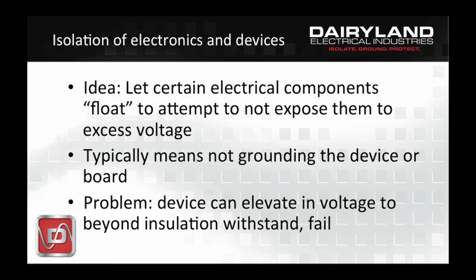Electronics and their failures can be associated at times for users with lightning events and AC fault events. Sometimes in order to deal with that, users might think of leaving their electronics to float electrically and not bond them to certain structures in an attempt to isolate them from harmful effects on those structures, say a pipeline. That usually means let's not bond it or ground it to something else. The problem is devices that are not bonded or referenced to other structures can rise in voltage beyond the voltage withstand of the insulation system or the insulation of the wires and eventually failing electronic components or the like.